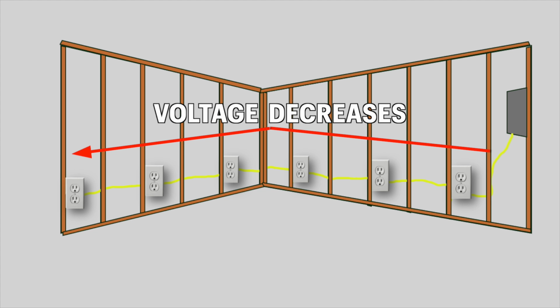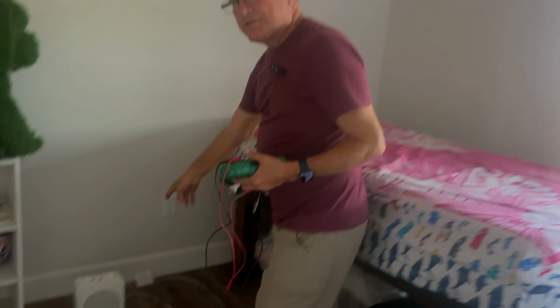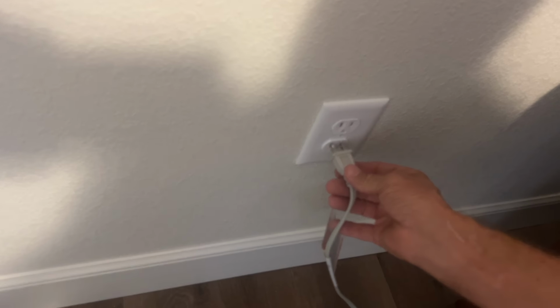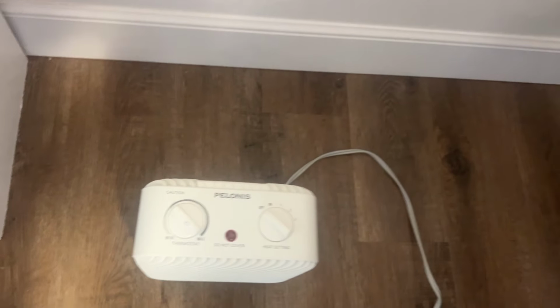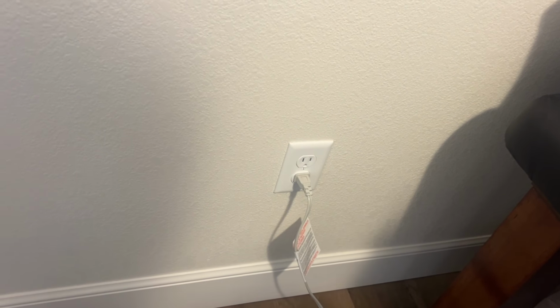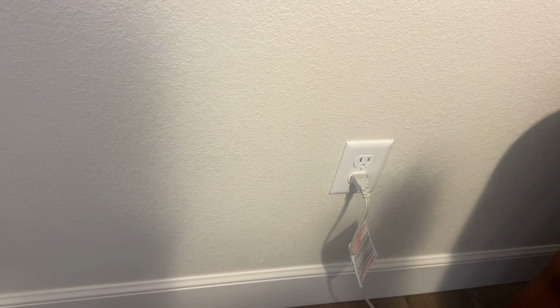The first thing we're going to do is measure the voltage drop on these receptacles. The further the receptacles are from the breaker panel, the more voltage drop there should be. But in order to create a voltage drop, I'm going to run a heavy-duty load on this circuit—I've got a space heater here. We know that voltage is equal to current times resistance, so the more current flowing, the more voltage drop we'll get. The further we get from the breaker panel, the more resistance we should have, so the more voltage drop we should have. I'm going to turn this on.